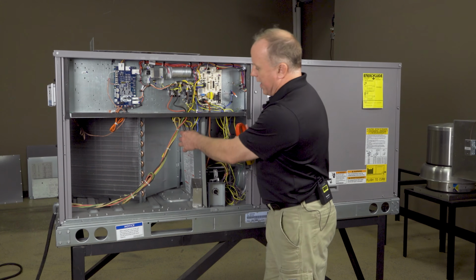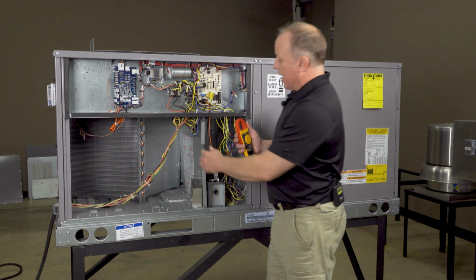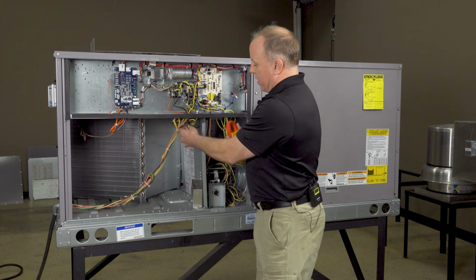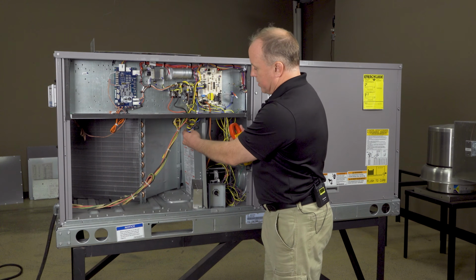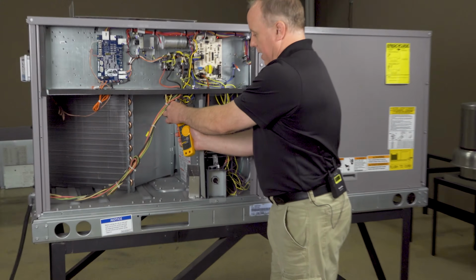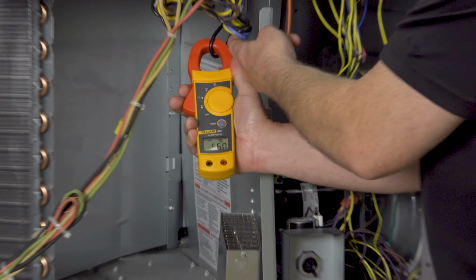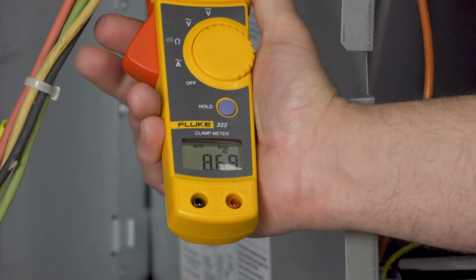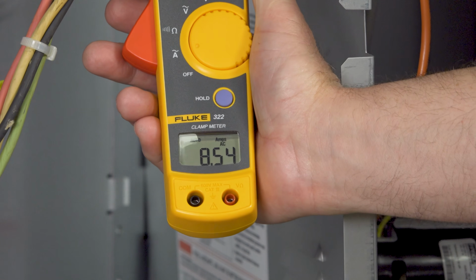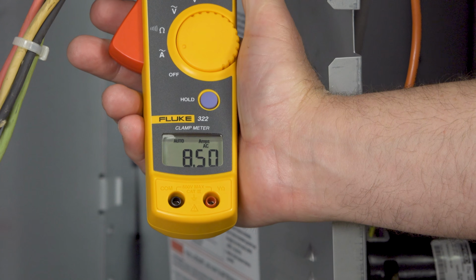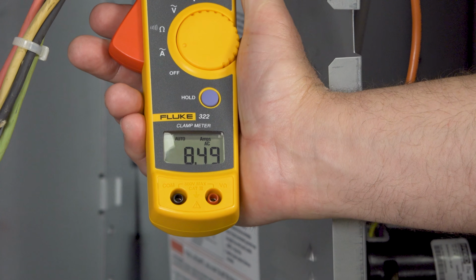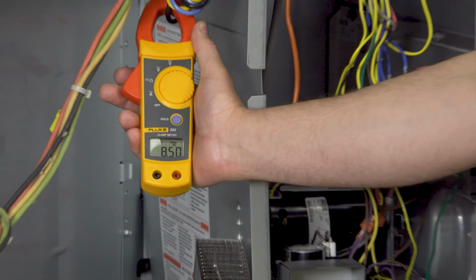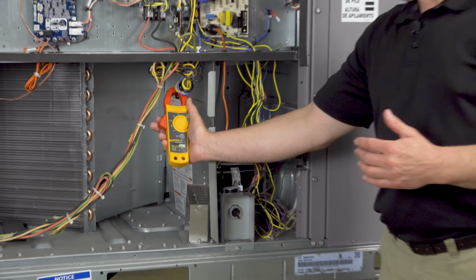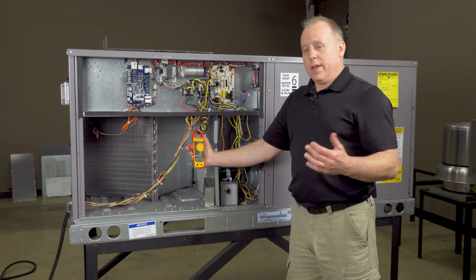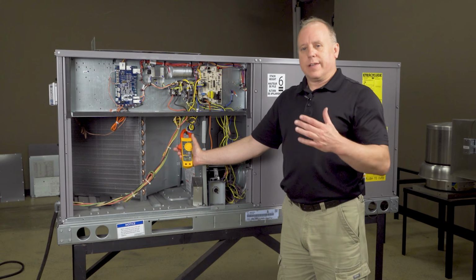Our wires are going right out in the same direction because those are located in the same section of the unit. So I'm going to come over to our compressor wires, and same thing. I'm going to get on one of those wires, just one. So I'm on the black wire. It chose the black again. And right now, we're showing about 8.5 amps, and that's as we're running. So this is below what we're rated at on this unit, which is not really an issue. We're not really under much of a load in here at all.